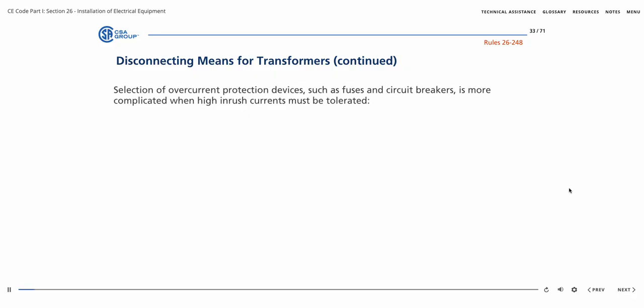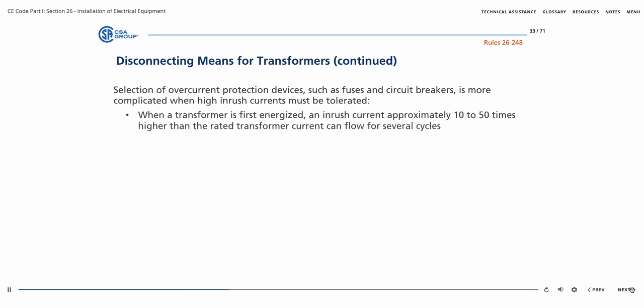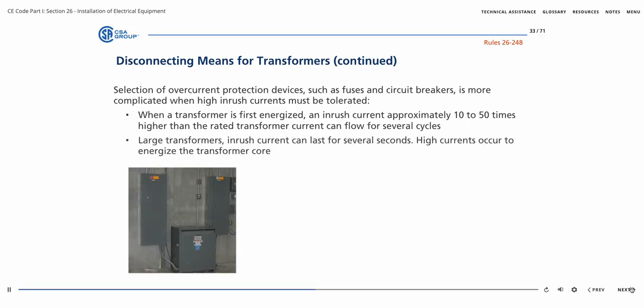The selection of overcurrent protection devices, such as fuses and circuit breakers, is made more complicated when high inrush currents have to be tolerated. The overcurrent protection is to react quickly to overload or short circuit faults, but should not interrupt the circuit when the usually harmless inrush current flows. When a transformer is first energized, an inrush current approximately 10 to 50 times higher than the rated transformer current can flow for several cycles. For large transformers, the inrush current can last for several seconds.